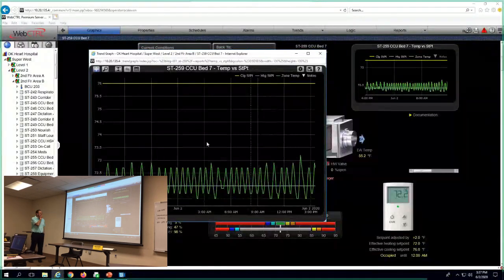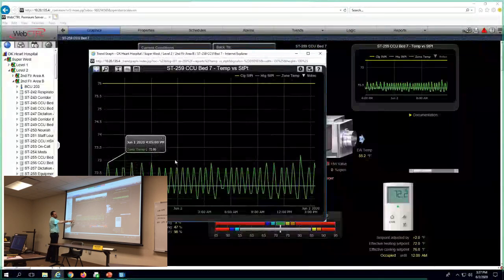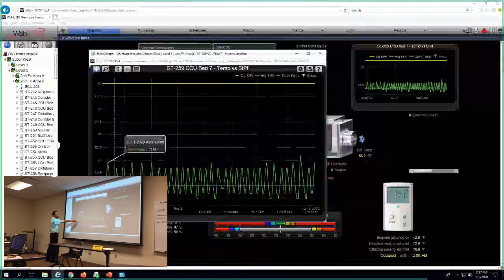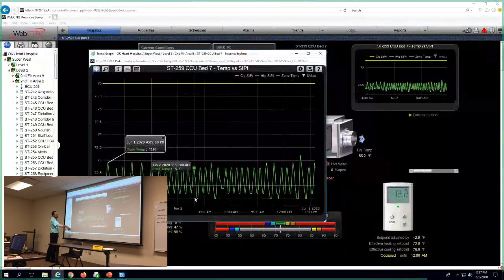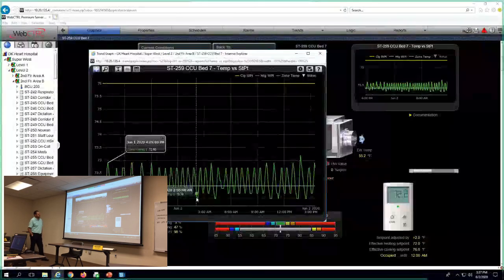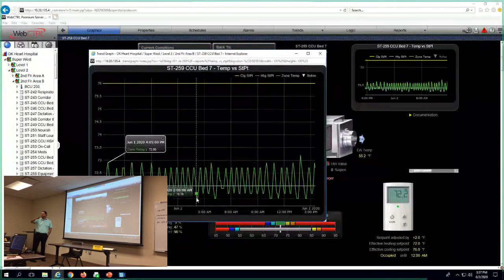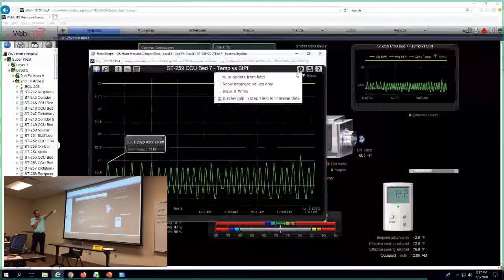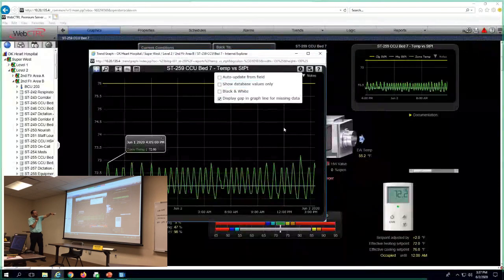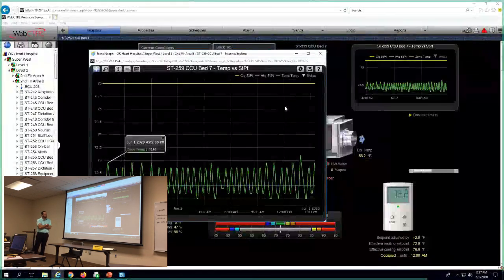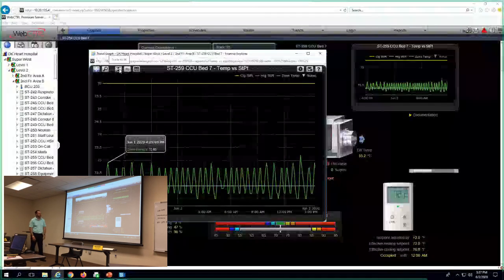Yeah, okay. So that's another thing, this swing may look like a lot, but I don't know how much. Go down to the bottom here, how long is that? Degree in about an hour. So it's maintained within a degree over an hour. That curve, we can adjust the settings of. Go up here and click on that little deal. No, I just lied to you. We can change the way it looks, make it look more like a hump. Basically the resolution, we can change it, make it look like whatever.